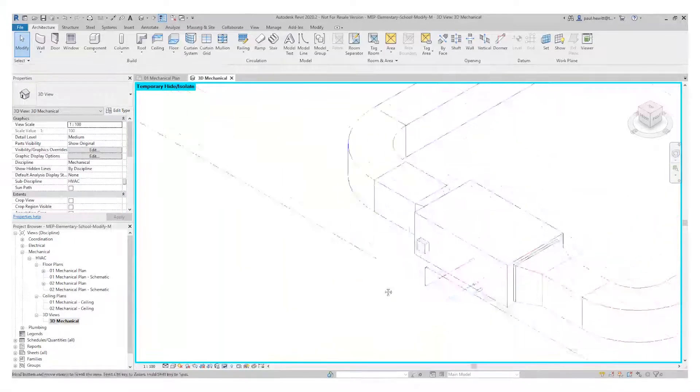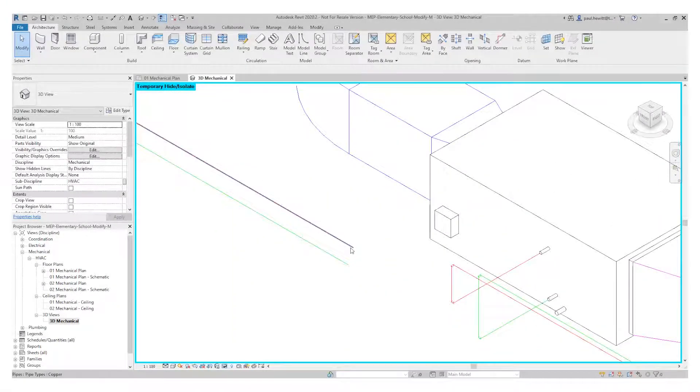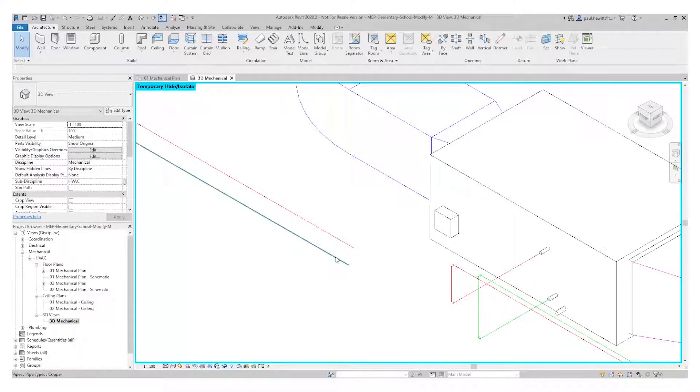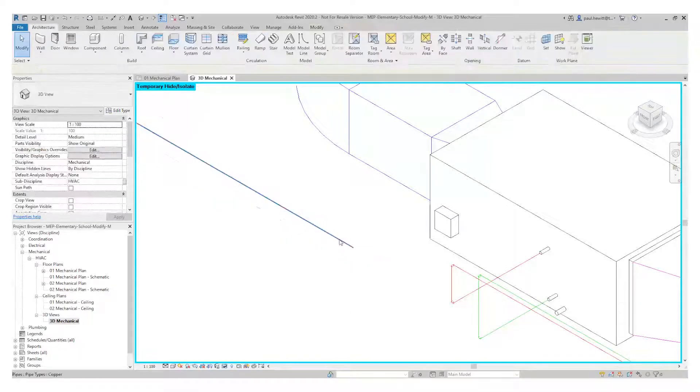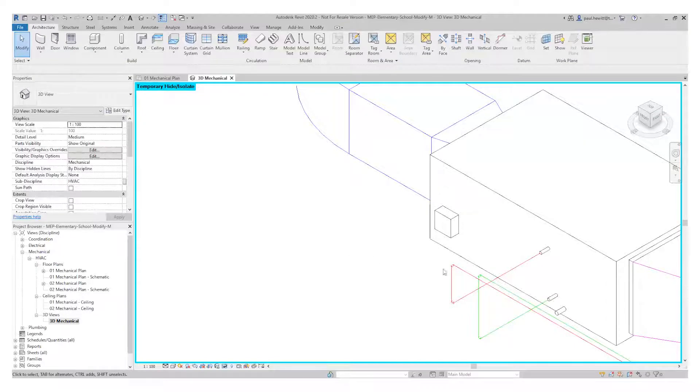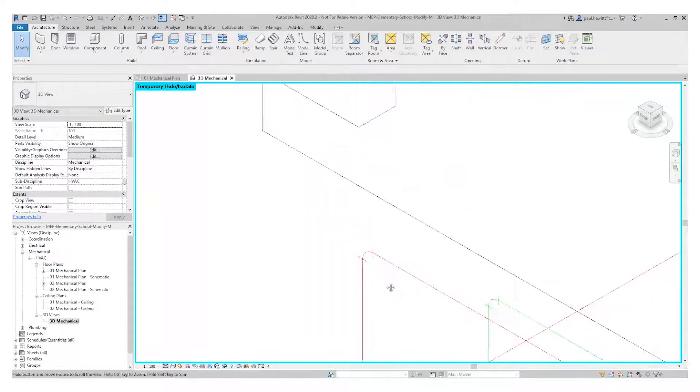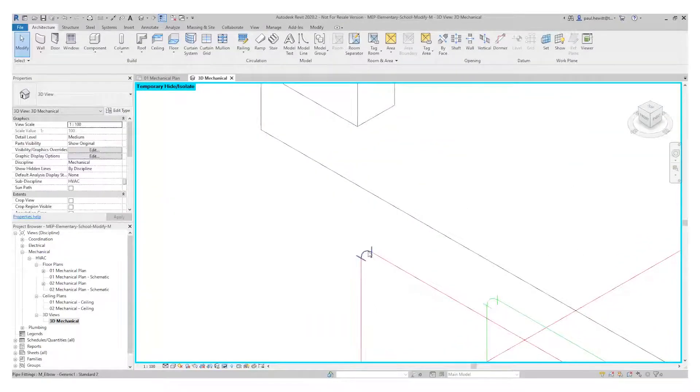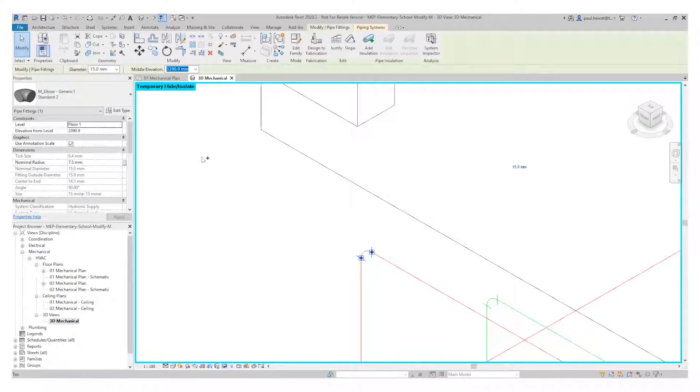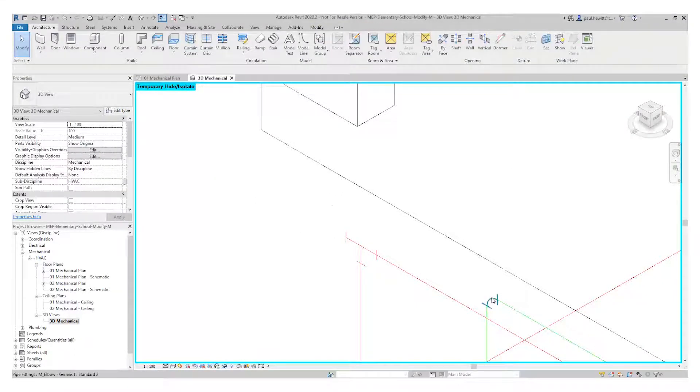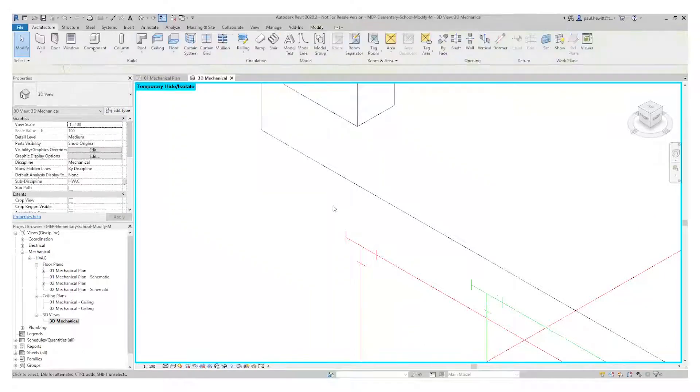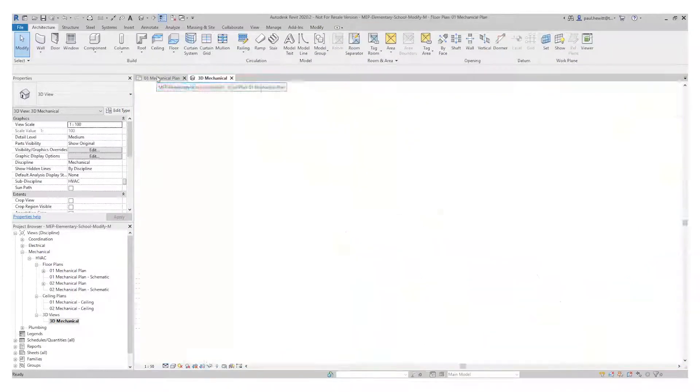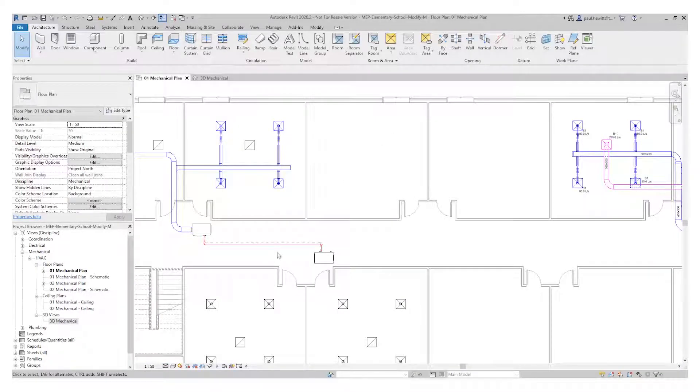So let's zoom in to where these two pipe runs are. Now we've got a bit of a job here to connect these up together. So what I'm going to do, making this easier, I'm actually going to delete these two pipe runs, like so. And then I'm going to actually change these bends here, just by selecting them and then select the plus that appears. And this changes the bend to a T piece.